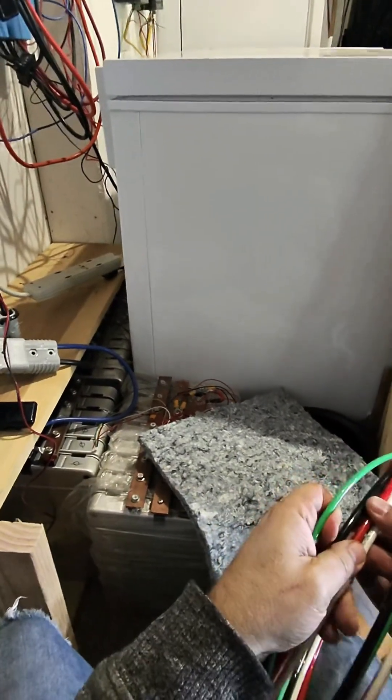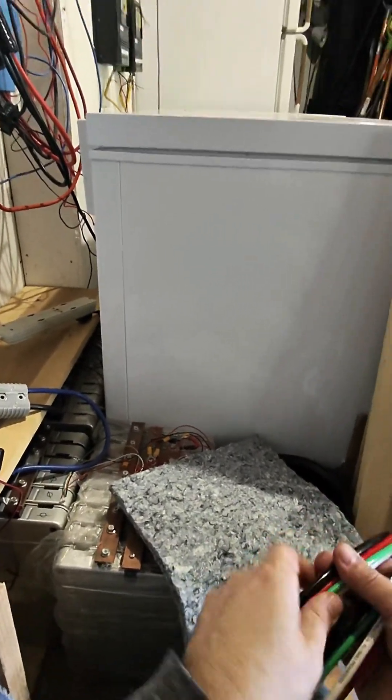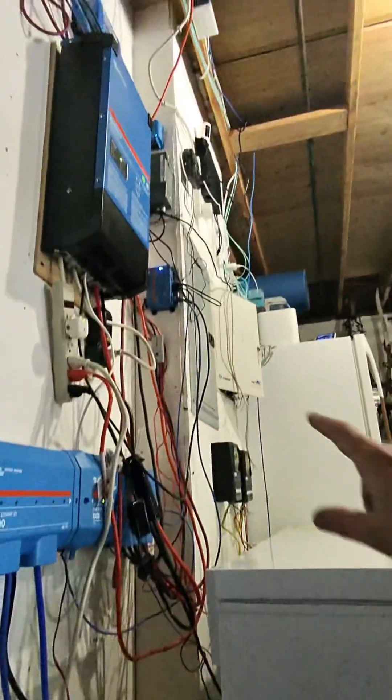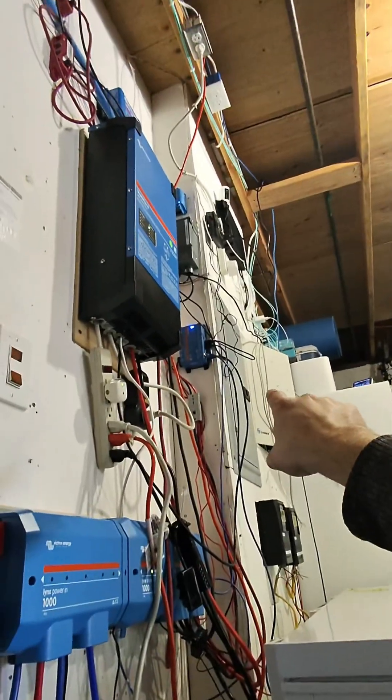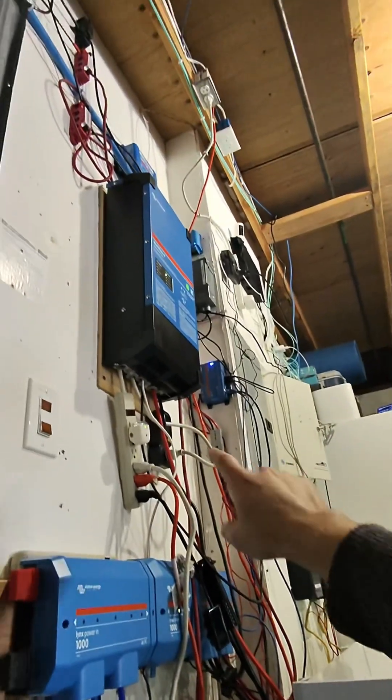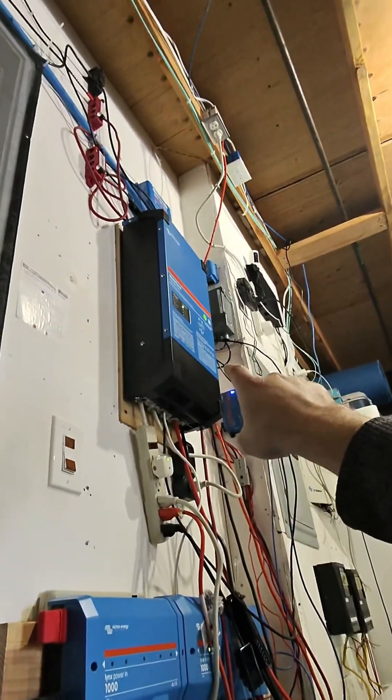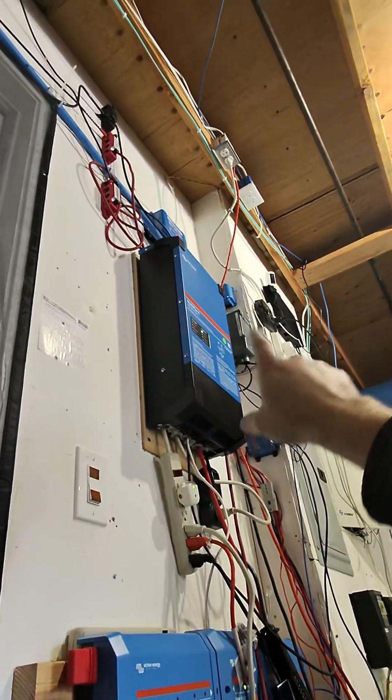So it's three 6 gauge lines, one 8 gauge line, that'll go from the power panel into the two phase input of that Multi Plus 2.